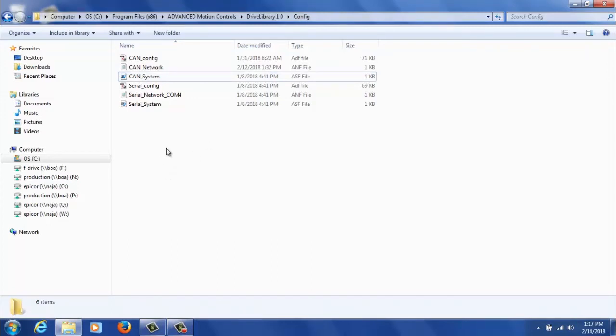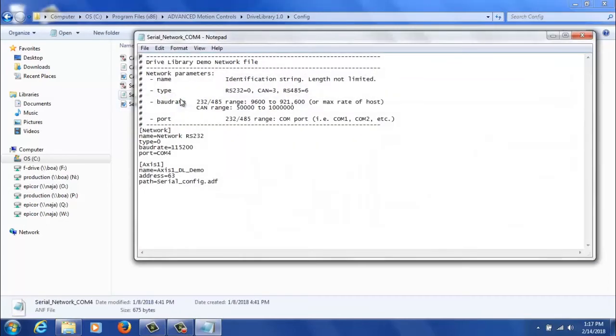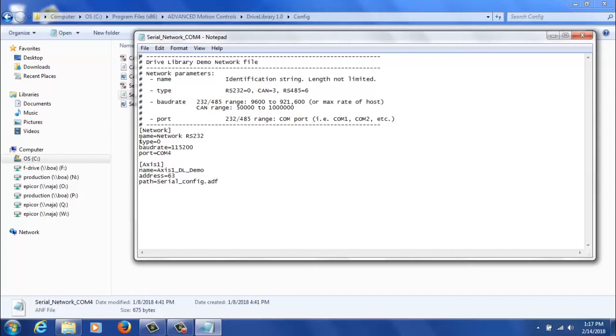So when you're going through serial, the first file you're edit is the serial network COM4. This file has all the network parameters and axis parameters. And when you first look at the network parameters, the first thing you'll see is the network name. This can be configured to anything you want. The type for RS232 is 0. And then you'll set the corresponding baud rate to match what's on the drive.